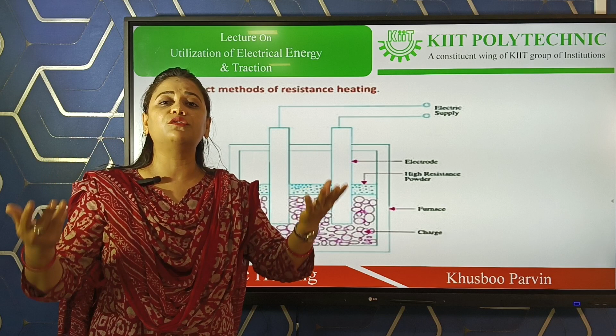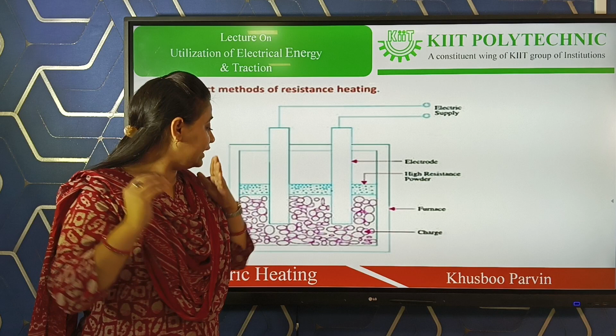When a single phase supply is given to the electrodes, current will flow from the positive side to the negative side through the body of the charge. When the current passes through the body of the charge, as we know the charge is a material which has a very high amount of resistivity, it will produce I squared R losses according to the Joule heating principle. When the I squared R losses occur, they occur in the form of heat. So that heat is further used for heating the metal or the charge placed at the bottom of the furnace.